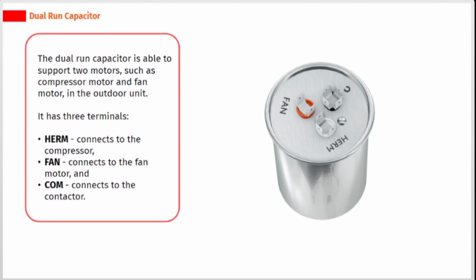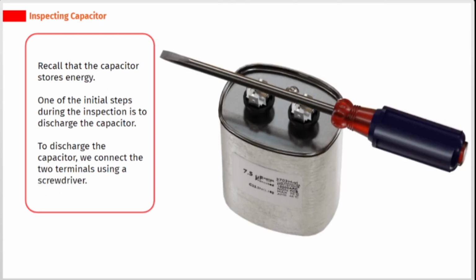The dual run capacitor is able to support two motors, such as the compressor motor and fan motor, in the outdoor unit. It has three terminals: HERM connects to the compressor, FAN connects to the fan motor, and COM connects to the contactor. Recall that the capacitor stores energy.